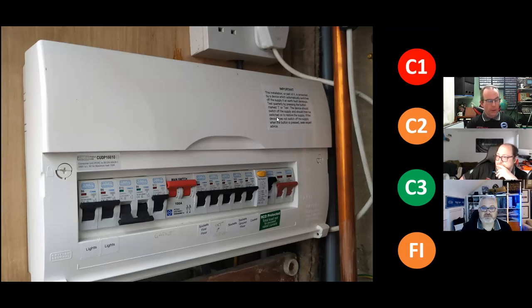Shall I throw some controversy in this? Yes, go on. Let's throw some controversy. So, I've got the Codebreaker book out, which defines this as a non-codable observation. I'll read it out. Proximity of gas services to electrical wiring is not strictly a 7671 issue. Regulation 528.3 goes some way to cover this. Regulation 528.3 defines this as proximity to services that produce heat, smoke, or fumes, which are likely to be detrimental to the wiring. I wouldn't say it's detrimental. I'd say you just can't get the cover off.